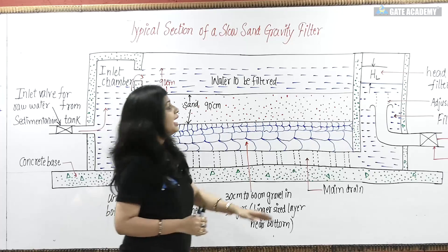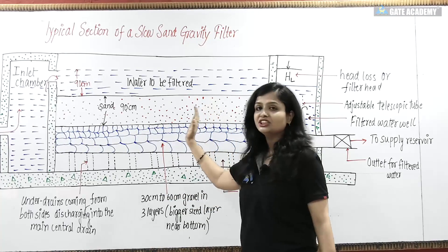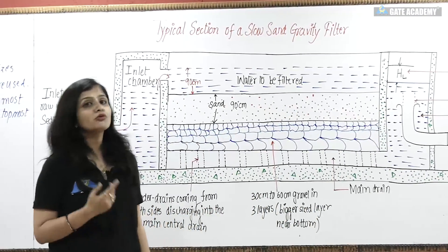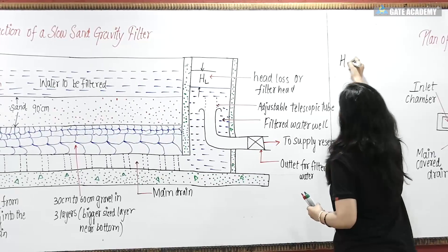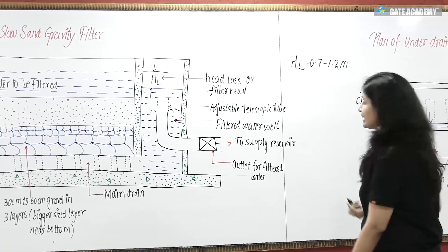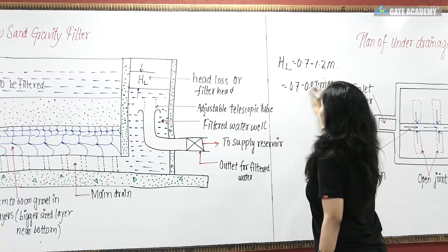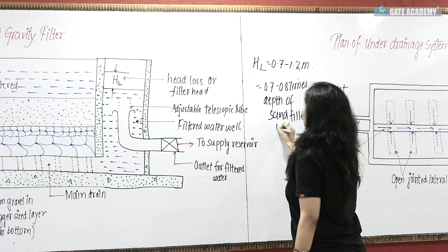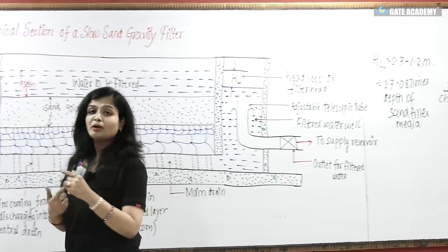When you repeatedly filter water, after a certain time the efficiency of the sand decreases. In that case, you have to clean your slow sand gravity filter. You know it is time to clean when the head loss reaches 0.7 meters — this initial value starts at around 0.2 meters. So when the head loss reaches this limiting value, you must take the filter out of service and clean it.